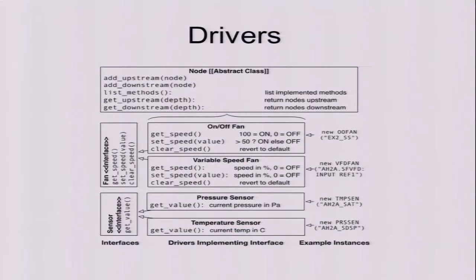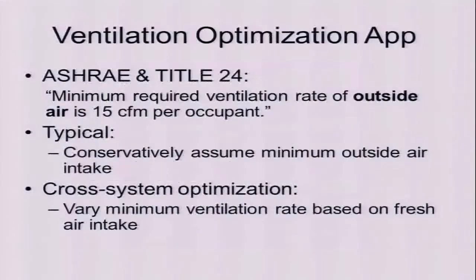In addition, there are a number of drivers that take that low-level BACnet and give you general methods. The key idea is that drivers are built up hierarchically using interfaces—standard good computer science design. For example, all fans might have a get-speed and set-speed method, which could be implemented whether you have a tri-speed fan or a variable-speed fan, controlling to whatever its capabilities are. That way, a program that needs to control the fan can run across different buildings.